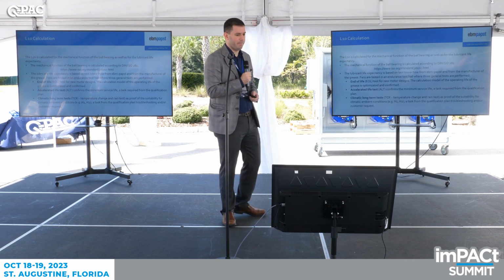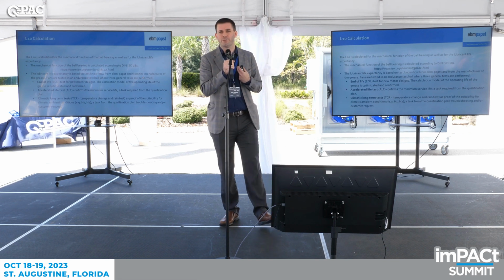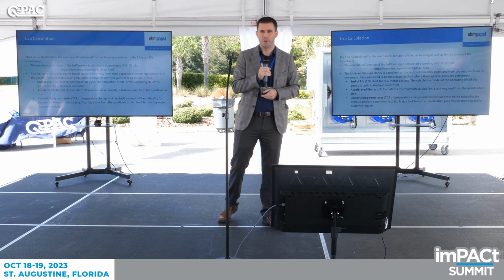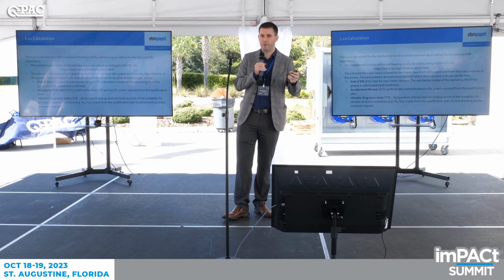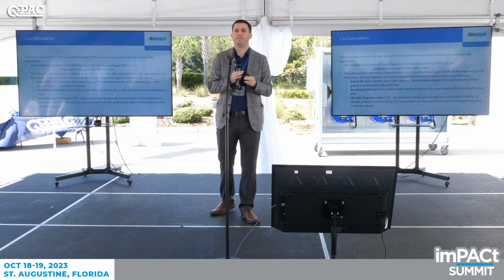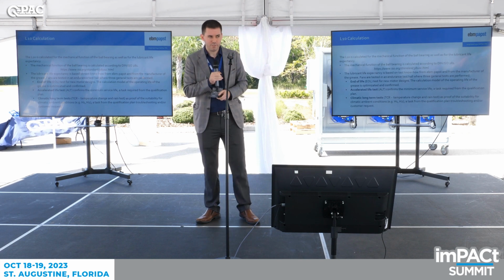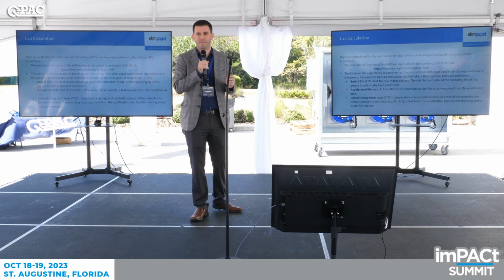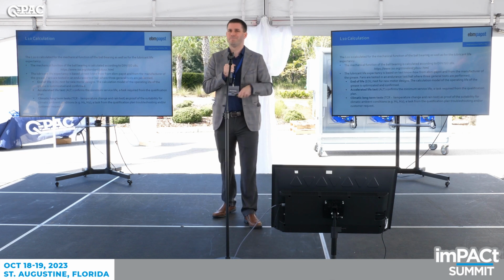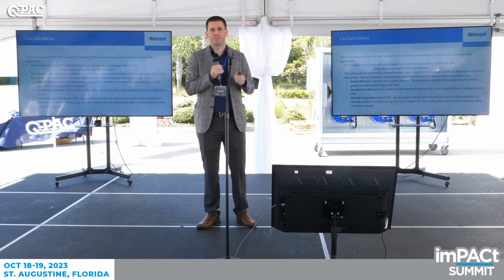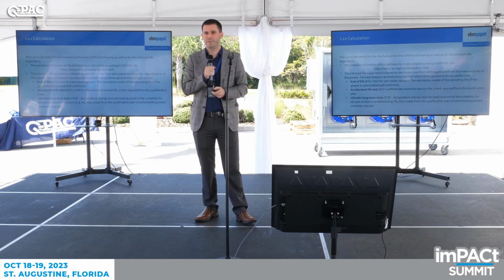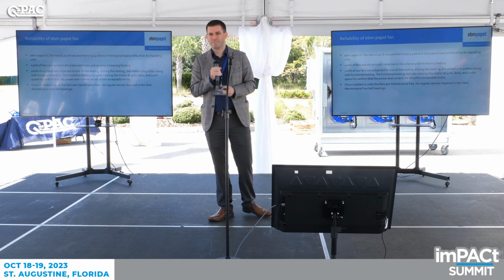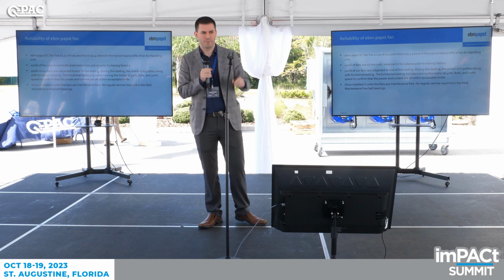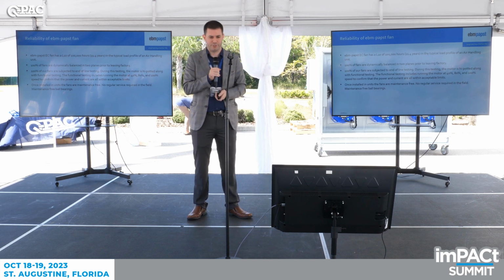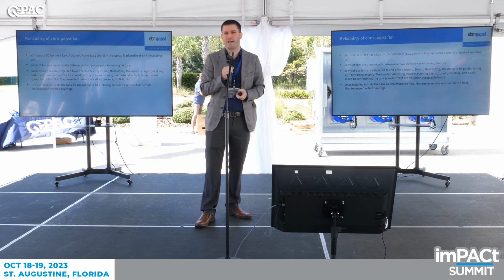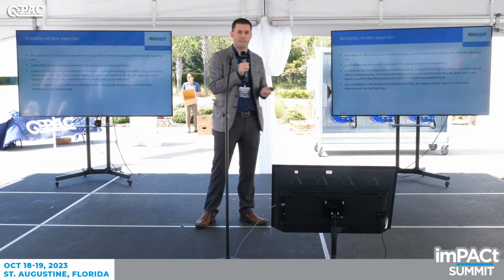Okay, so getting into the lifetime comparison. When we talk about lifetime of EC motors, we're normally talking about the L10. L10 means the amount of hours at which 10% of the sample field would fail. So 90% would still be running, 10% would have failed at this time. We get these numbers from our suppliers, from testing, and we're able to determine the different variables that go into this calculation. So we find, in an air handler with a typical air handling operating curve of what speeds it's operating at and what temperatures, we get a lifetime of approximately 100,000 hours for the L10.